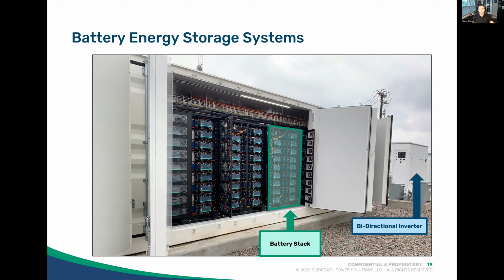As the frequency deviates from 60 hertz, they issue commands in very rapid fashion to different generators, for the most part still gas generators, adjusting their output up or down to manage that frequency back to 60 hertz. Depending on the system, those signals can come as quickly as every 5 seconds. Our project in Myersdale, Pennsylvania receives a new set point from PJM every 5 seconds.